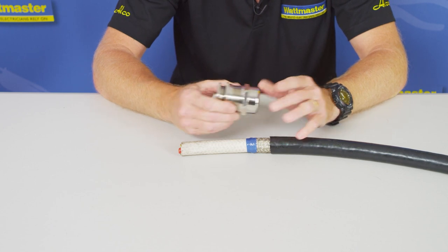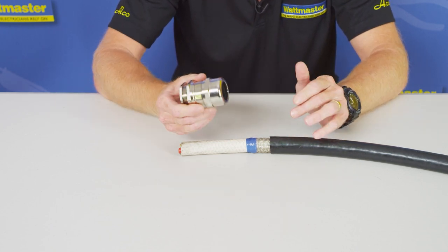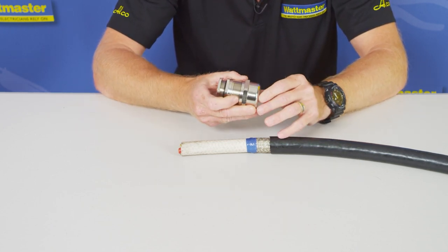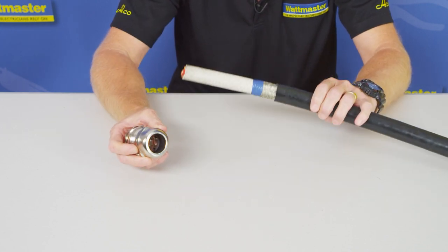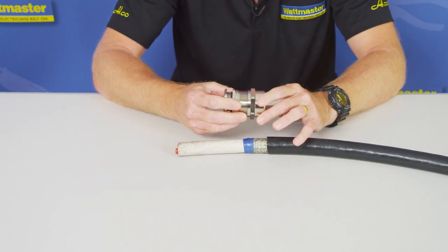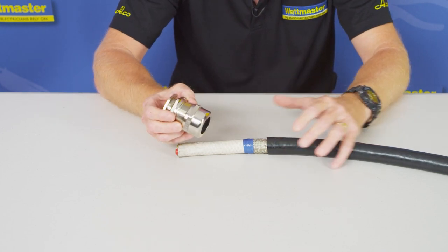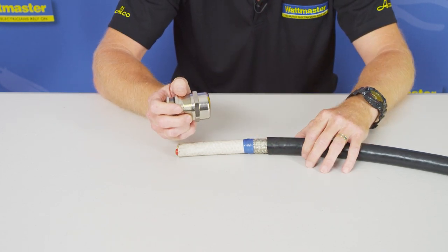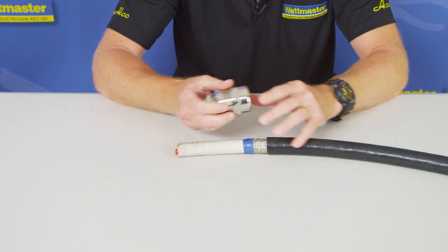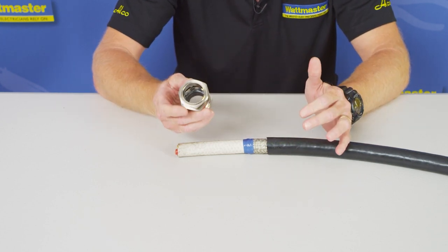So what we're going to do today is show you how to use firstly the EMC type gland with the fingers inside. I've prepared the cable earlier. What we're trying to do is create that Faraday cage for the cable and continue that braid through into the enclosure and onto the earth.